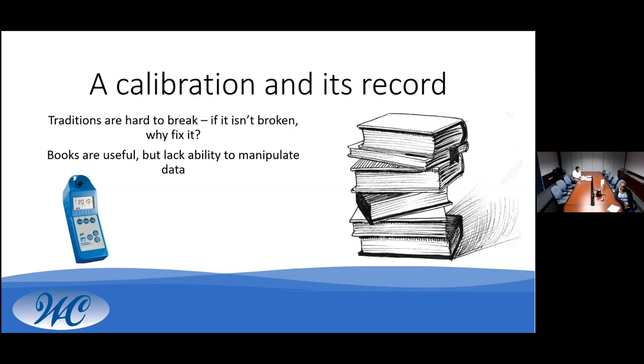Section 6.4.7 of the standard requires that our instrument's calibration program be reviewed and adjusted to ensure confidence in the calibration status. The failure showed that we needed to change our 30-day interval to a more appropriate length of time that would prevent instruments from being found out of calibration. However, our calibration records felt like they were locked away in an open notebook. When we began reviewing our written calibration data, it became evident that the resources required to flip back and forth between records to determine trends and risks with each instrument are immense. If I could roughly estimate the time spent to write up the book, calibrate the instrument, perform relevant calculations by hand, review historical data, then assign an appropriate interval could take at least an hour.